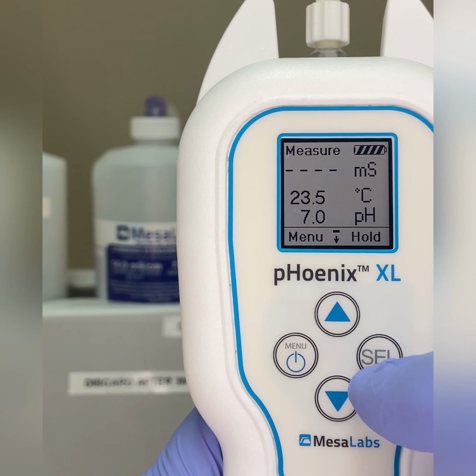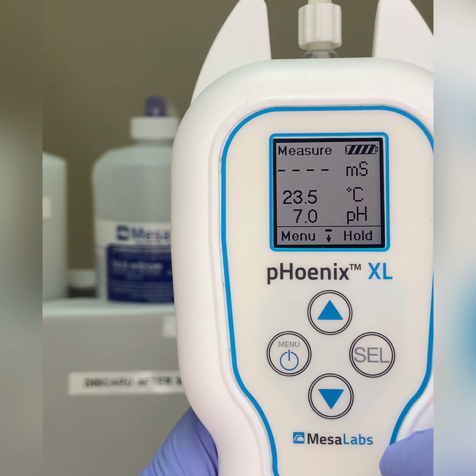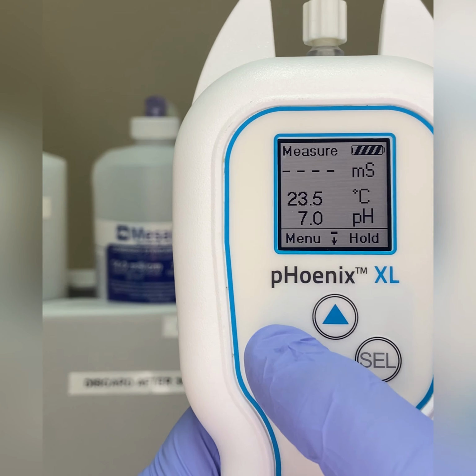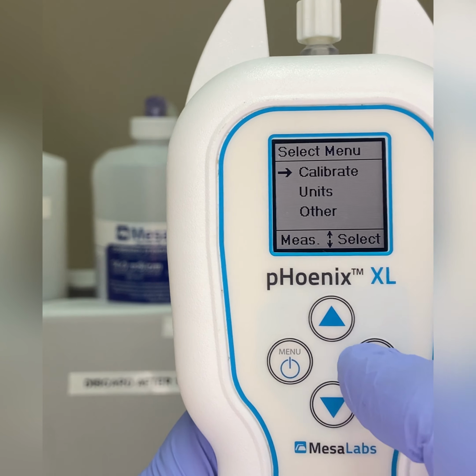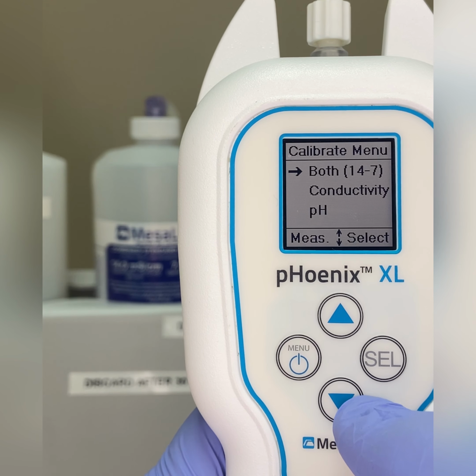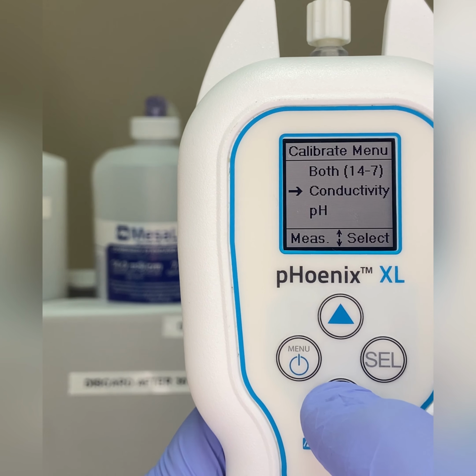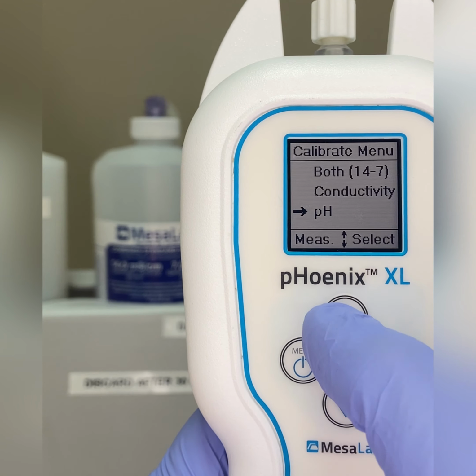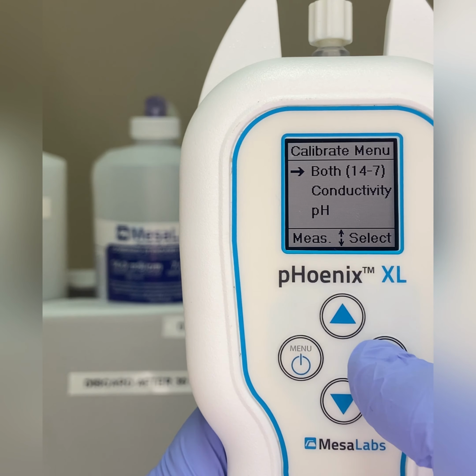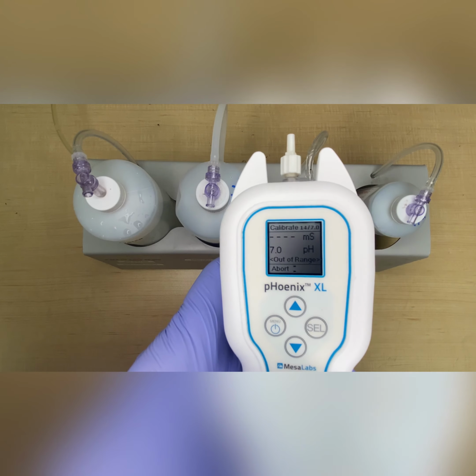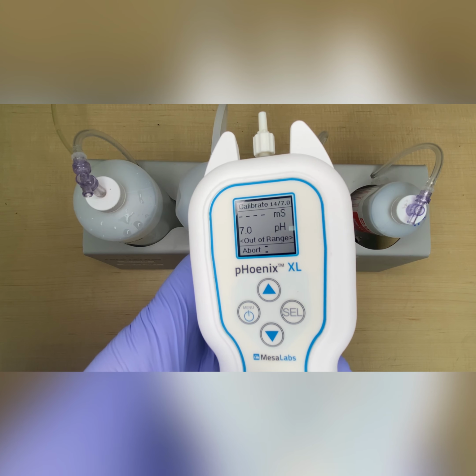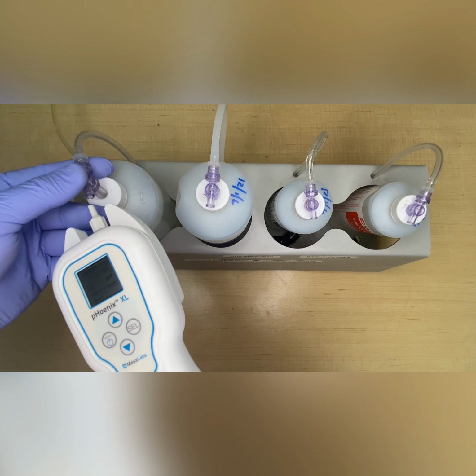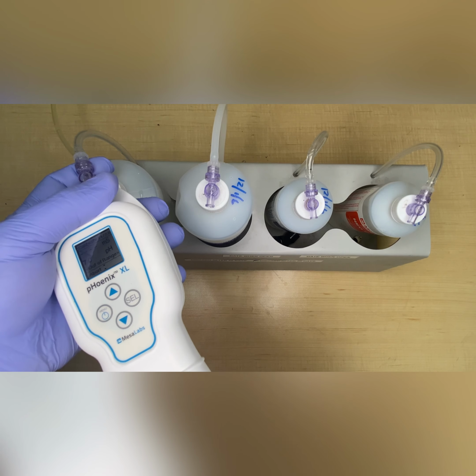If we press the menu button, it'll bring us into the menu screen where we can select Calibrate. And from this menu, we can calibrate both, or we can calibrate them separately. We're going to go ahead and select both. Next up, most likely you're going to have NeoCare left over from the night before, so you're going to want to rinse that out with some RO water.